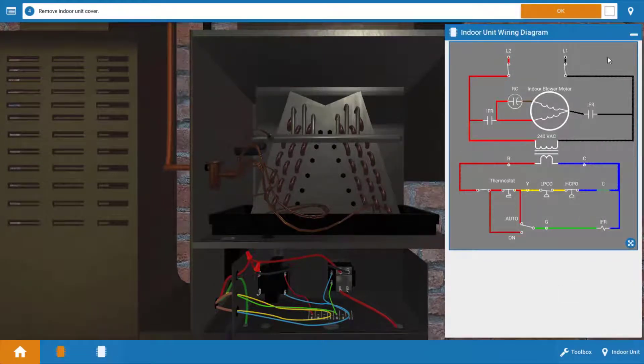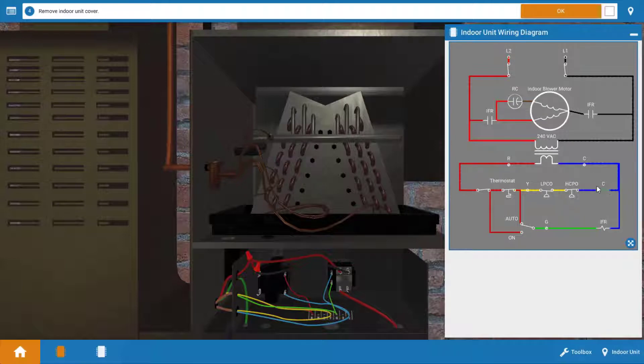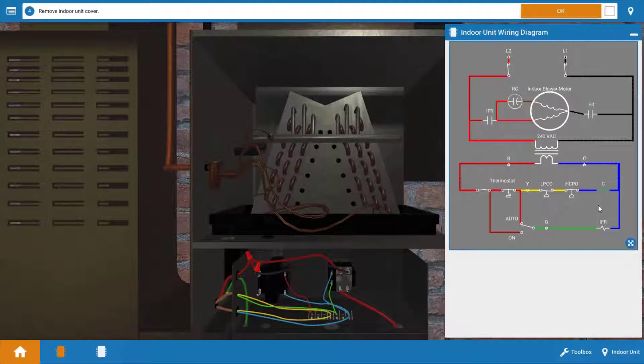So the indoor blower motor shown here on the top is not running. However, we know this contactor coil here at the bottom is getting power because the outdoor unit is on and this contactor is actually the relay that controls the condenser fan and the compressor. So what do we got for possible causes? Well, it could be the blower motor itself.